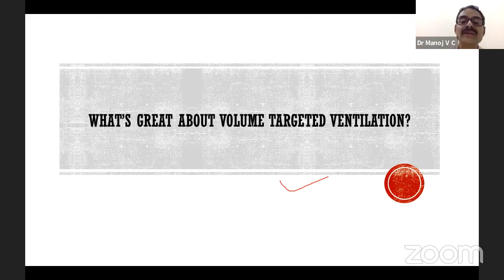Okay, now for the last part we will spend another 2 minutes on what's so great about volume targeted ventilation. We said that the limiting variable is always pressure, but what is volume targeted ventilation? Even though you have kept a PIP limit or pressure limit, you call it PIP max, the maximum pressure the baby is allowed to breathe at, you don't keep a minimum or mandatory pressure. Which means that you set a tidal volume, and when the tidal volume is reached with any pressure before that, you immediately stop the pressure at that point. That is the hybrid mode. So this is called targeting volume.